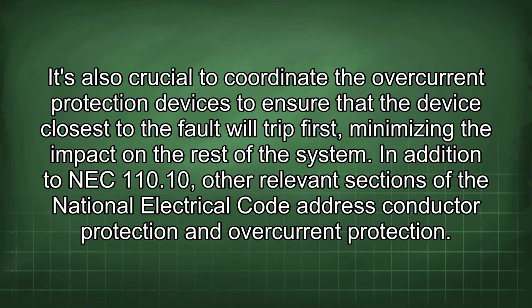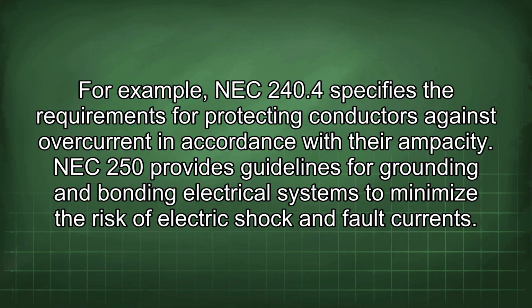It's also crucial to coordinate the overcurrent protection devices to ensure that the device closest to the fault will trip first, minimizing the impact on the rest of the system. In addition to NEC 110.10, other relevant sections of the National Electrical Code address conductor protection and overcurrent protection. For example, NEC 240.4 specifies the requirements for protecting conductors against overcurrent in accordance with their ampacity. NEC 250 provides guidelines for grounding and bonding electrical systems to minimize the risk of electric shock and fault currents.